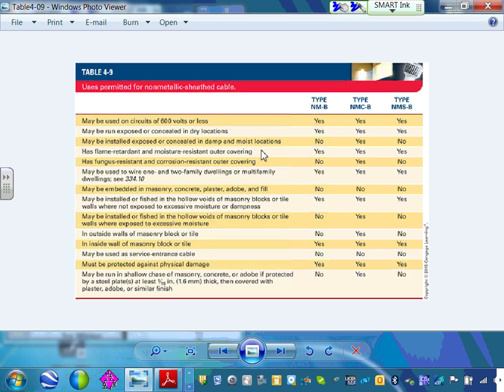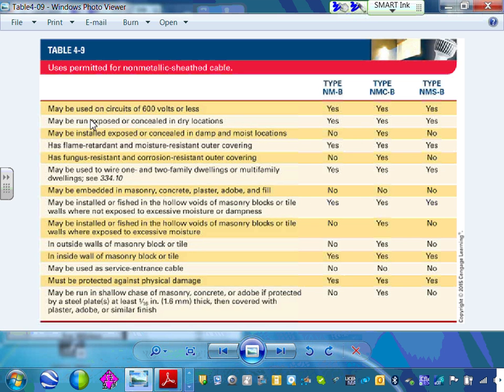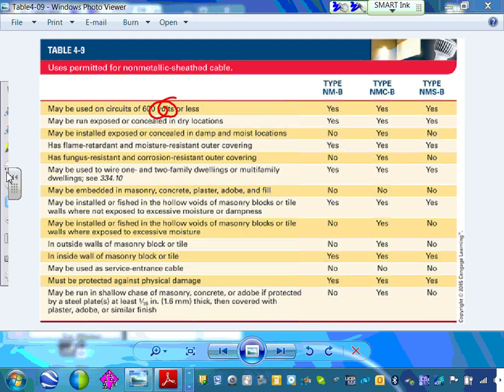Okay, so just to respect that one, I want to go over the regulations for this cable. Now, can you use it for medium voltage? Look at this, the first requirement. Can you use this for medium voltage, higher than 600 volt? Can you guys see that? No, very clearly it's limited.